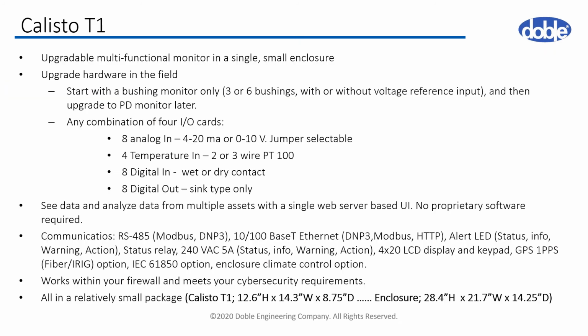This has been a very brief look at the Calisto T1. The T1 is a powerful monitoring platform with a relatively small footprint. This gives the user more options for the location of the monitor. The T1 can be a simple function monitor, as in one slot of I/O, and later a PD monitor, a bushing monitor, and/or I/O can be added. All the upgrades can be done in the field. With the T1's ability to accept third-party monitors, its usefulness is only limited by the user's imagination and the third-party monitor's ability to communicate with the T1.